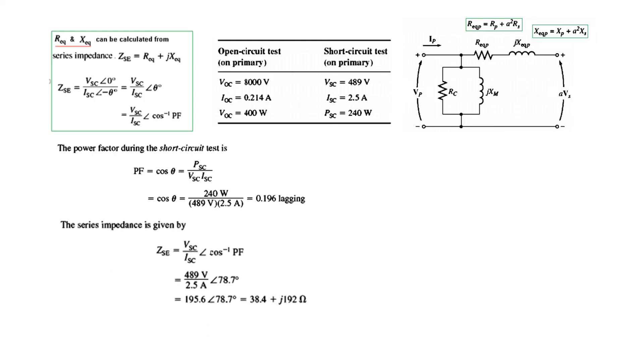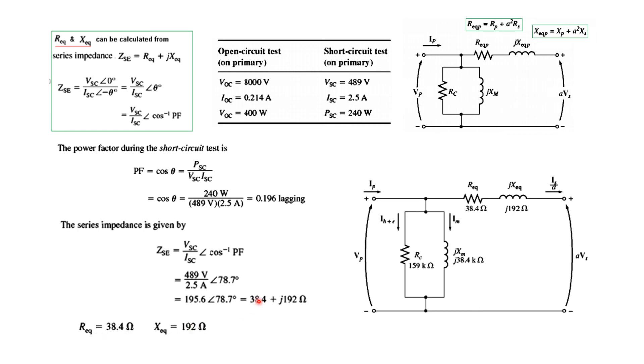And now we will find ZSC by using this formula. So ZSC is VSC over ISC cos inverse power factor. And plugging in the values. This power factor when we plug in, take cos inverse, it will be 78.7. So when we convert the value into a rectangular form, we get these two. And this is the real part and this is the imaginary part. And so we can say that the real part is equal to this one, the R equivalent is equal to 38.4. And X equivalent is equal to the imaginary part 192.